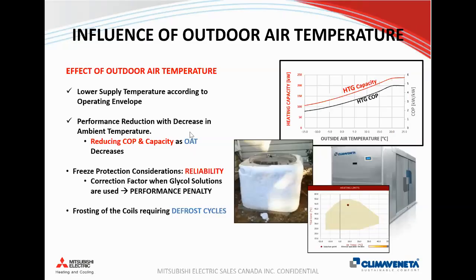So if we want to further understand the influence of outdoor air temperature on heat pump systems, we know that we have an operating envelope that we have to understand and deal with, and select our temperatures according to this. We also know that our heating capacity and our heating COP are going to fluctuate according to outside air temperature, and typically they'll decrease in curves that look like this. The other thing to keep in mind for air-to-water heat pump systems is, contrary to chillers, if you're going to have cooling available year round, typically that chiller outside would have glycol in the system, or in some buildings they might drain that system and not operate them during the winter time.